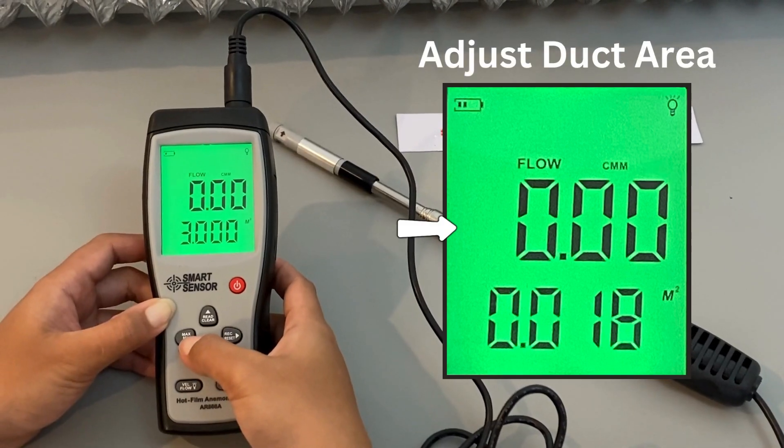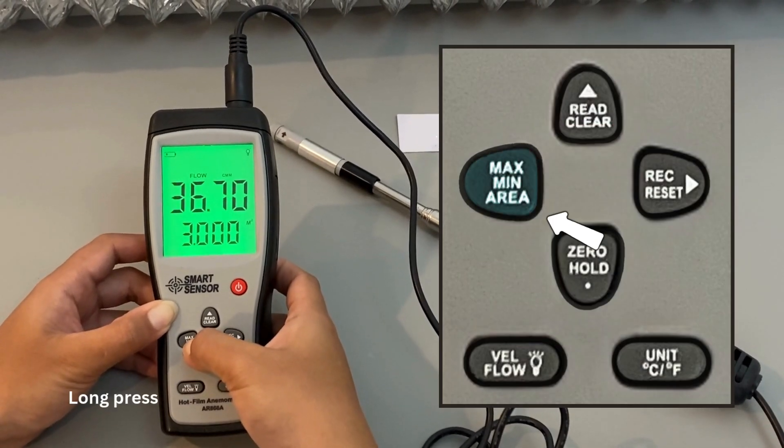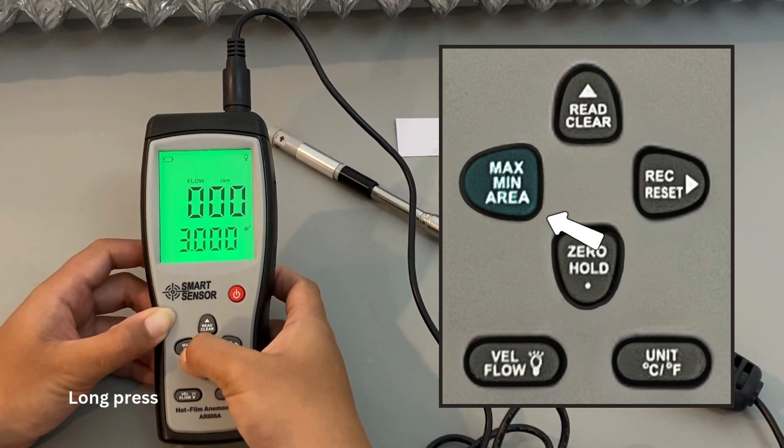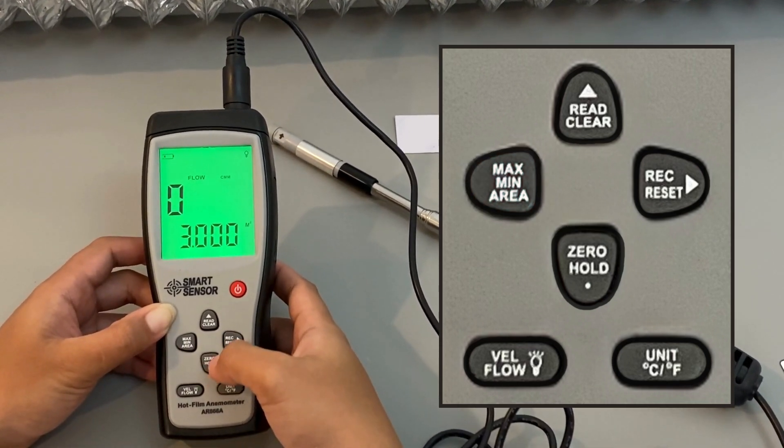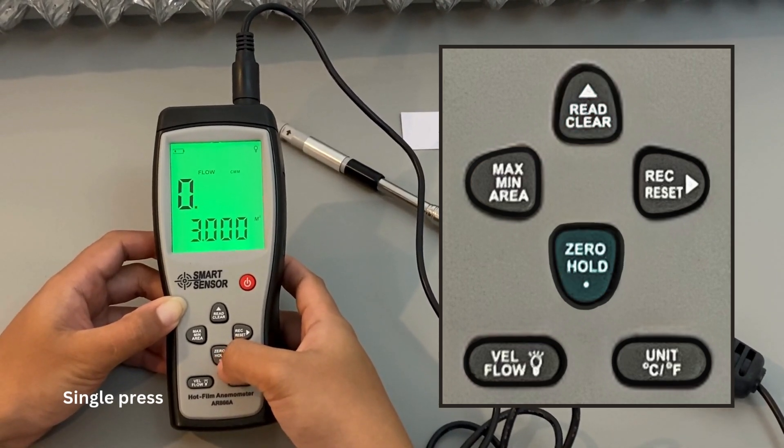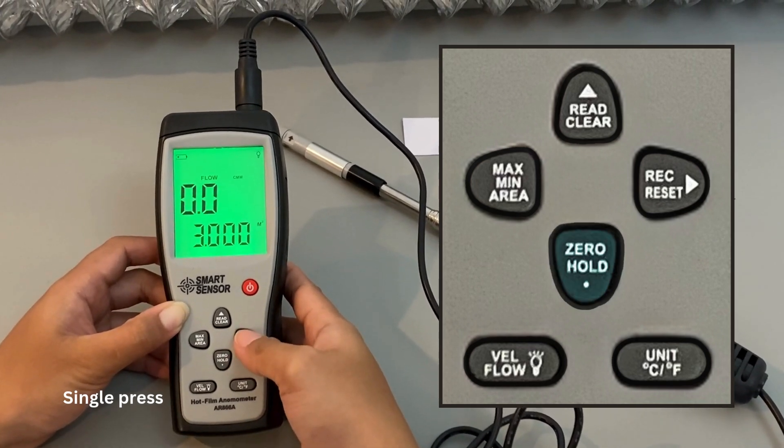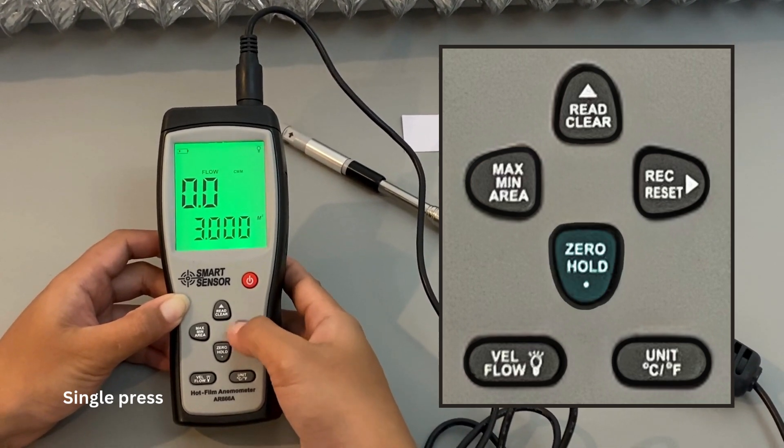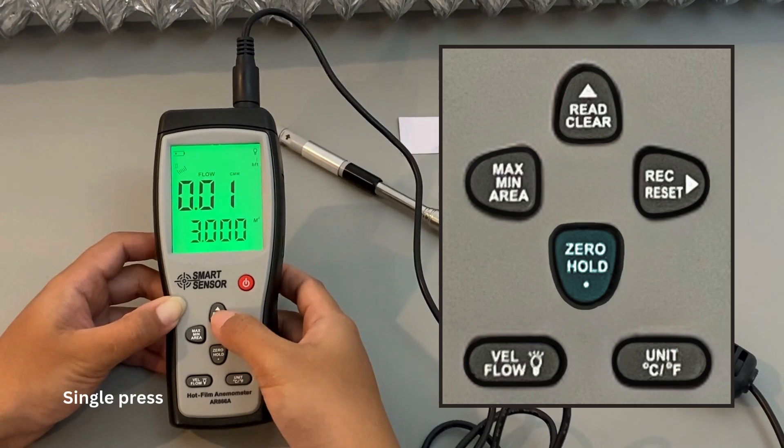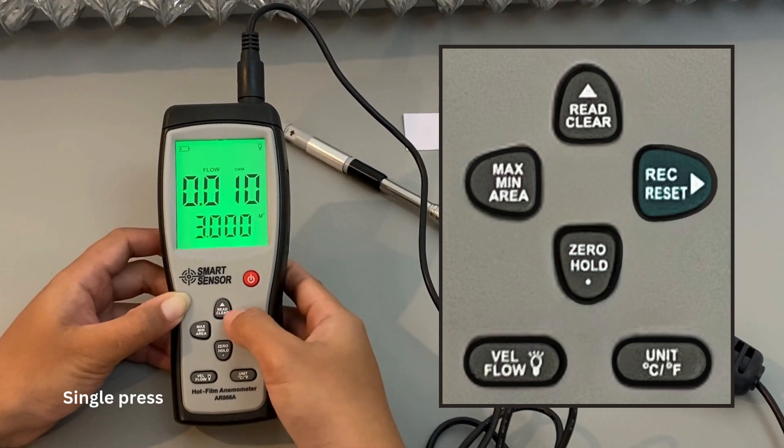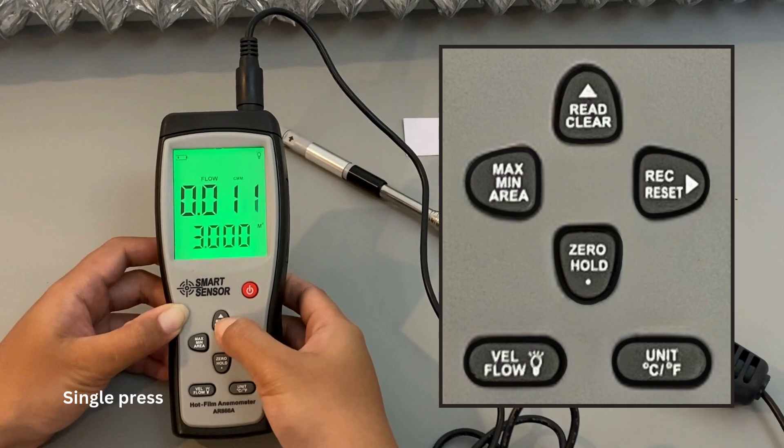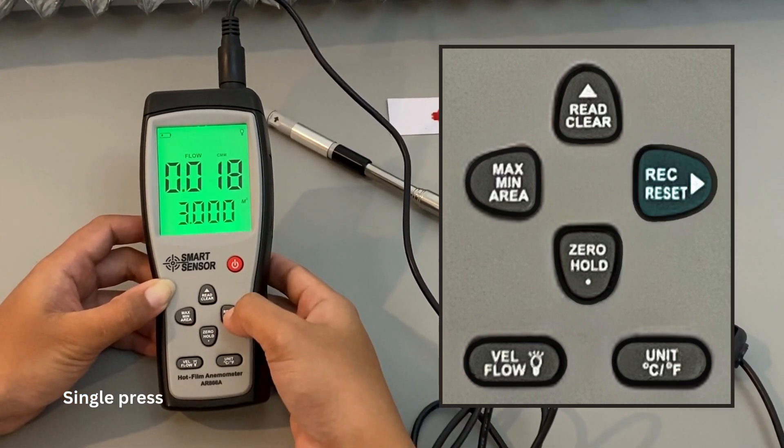Next, we will adjust the duct area. Press and hold the area button for three seconds to enter editing mode. Now, use the up and down buttons to adjust the duct area value to your desired number. If you need to add a decimal point, simply press the period button. Once you have entered the correct area value, press the reset button to set the value. And when you're done, press reset again to return to the main display.